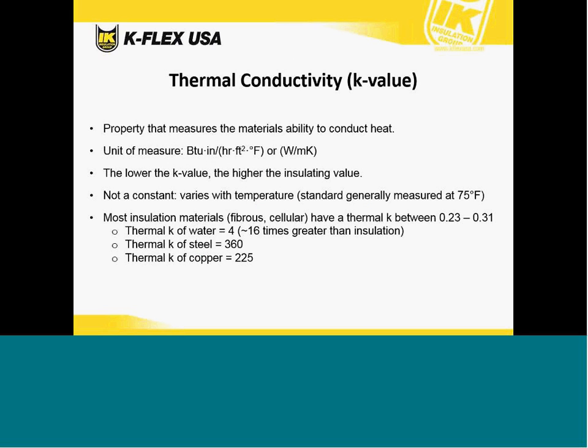So let's talk thermal conductivity. This is one of the most important aspects of the insulation system. It's the property that measures the material's ability to conduct heat. The units of measure in our system are BTU-inches per hour-square foot-degree Fahrenheit, or in the metric system, watts per meter-K. The takeaway here is the lower the K value, the higher the insulating value. So it's the inverse of the R value. With R, you want a higher number to get a better insulating value. With K, the lower, the better.